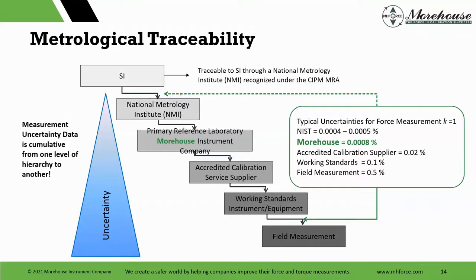The important thing here is that this is a pyramid. It all starts at the top. With SI at the top, as you disseminate down from these units, you have your NMI, NIST. Typically, NIST in this country, they are the best. We're chasing force over here, so NIST is 4 to 5 parts per million, depending on the day, temperature, humidity. Very tight. We sent most of our weights and frames to be calibrated by NIST. They were calibrated with uncertainties of around 8 parts per million. That's for a standard uncertainty.